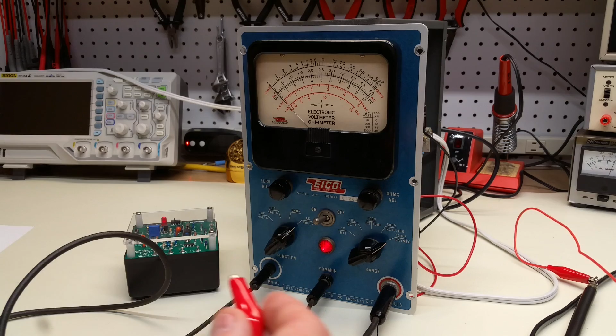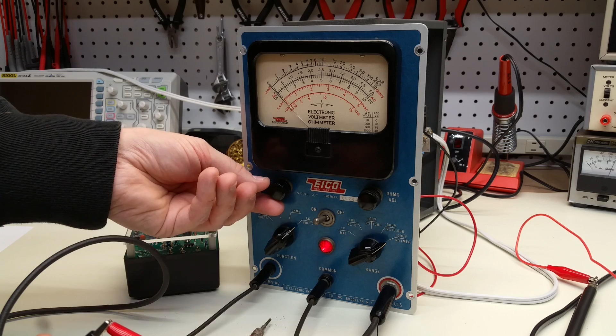To short the AC ohms test lead, that's now a black test lead, to the ground, and adjust the zero adjust control until it reads 0. And you see that, in fact, we don't actually have to do any adjustment. It's already set there.